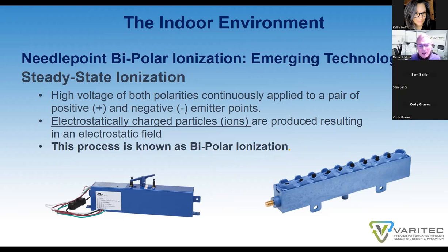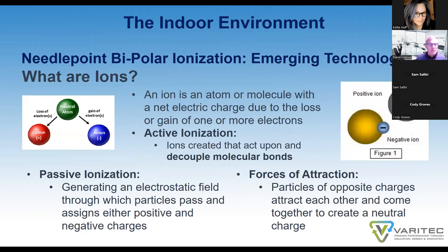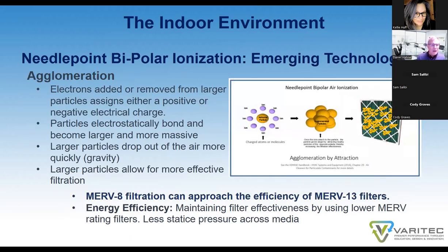Needlepoint bipolar ionization works by providing a high voltage charge to what are called ion emitters. These emitters actually ionize the molecules local to those emitters with positive and negative charges. And by the process of passive ionization, positively and negatively charged particles of contaminants and even pathogens potentially have a tendency to attract, agglomerize, become heavier, and fall out of the air, or are more effectively captured by filtration systems. So by the process of agglomeration through the use of ionization, this technology suggests that we can actually create a healthier environment and reduce the risk of infection through the process of agglomeration.